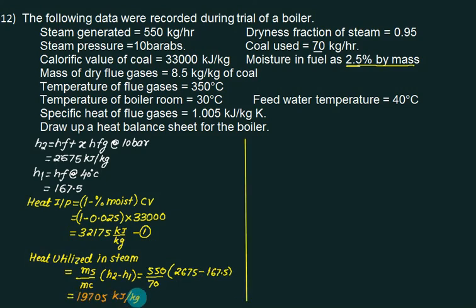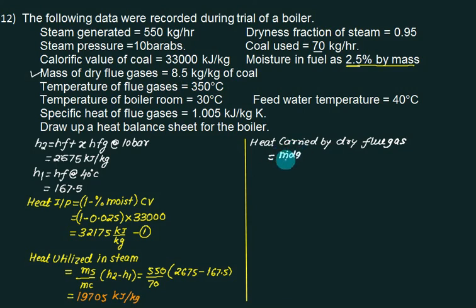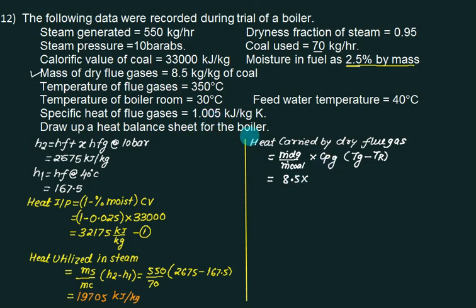Next, heat carried by dry flue gas: the mass of dry flue gas is given as 8.5 kg per kg of coal. Heat equals (m_dot_dg / m_dot_coal) × Cp_dry_gas × (T_flue_gas − T_room), which is 8.5 × 1.005 × (350 − 30) kJ/kg of coal.